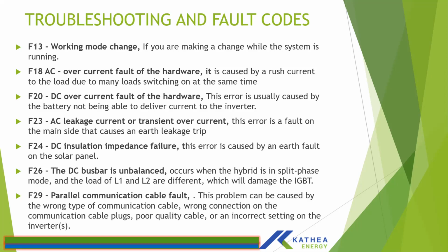And then DC overcurrent. This is if the inverter has a load demand which is quite high, and then it draws power from the batteries, and the battery can supply power to its capability. And then if that current is more than the DC rating of the inverter, it will give this fault. So that's where you need to install a fuse, such that if there is an inrush current drawn from the battery, you can trip that fuse and protect your inverter. Alternatively, if the battery is lithium, it would automatically switch off when too much inrush current is drawn from it.